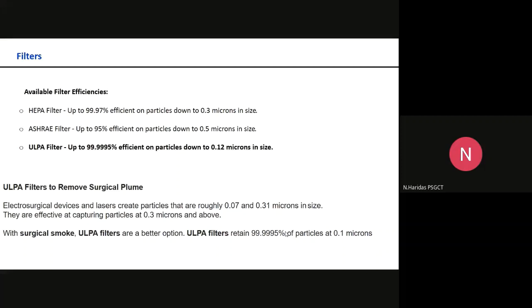So the suction systems remove the air, which has to be properly filtered. It can filter down particles up to 0.12 microns. The electrosurgical devices and lasers create particles that are roughly around 0.07 microns to 0.31 microns in size. These can be properly filtered out by using a ULPA filter. So, for filtering the surgical smoke, the ULPA filter is the best one. It is 99.95% efficient.